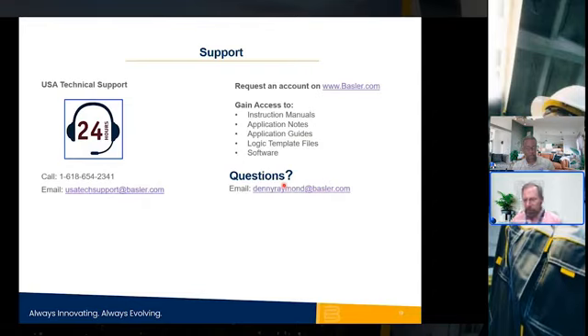Another question came in. How is an inverter-based resource different from a synchronous machine? A synchronous machine has inertia, an inverter-based resource does not. So that's one of the big differences. And as a result of that, they behave differently. So a synchronous machine is already spinning. It's easier to have it ride through a fault. And they tend to be able to contribute high levels of fault current, sometimes up to 8 to 10 times their rated current, to ride through a fault and clear the fault.